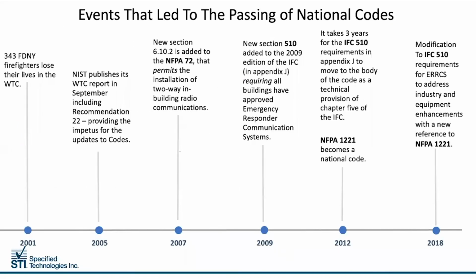After 9/11, it took 8 years for the International Code Council, the ICC, to introduce in-building requirements for public safety communications into the International Fire Code, IFC, in 2009. And then it only showed up in the appendix, which meant it was a recommendation available for adoption, not necessarily a requirement in the technical provisions of the code. Upon further modification, that language got moved to the technical provision of Chapter 5 of the IFC in 2012.